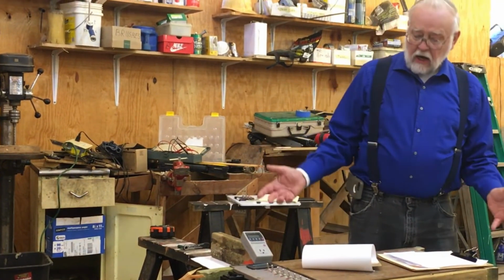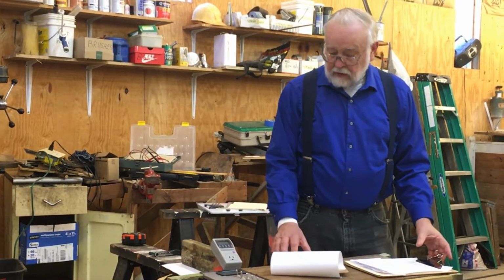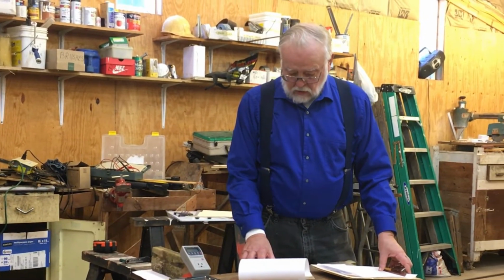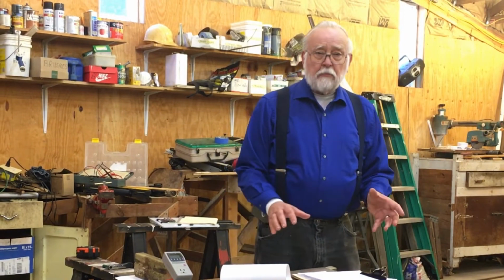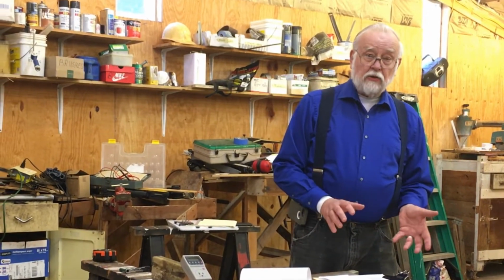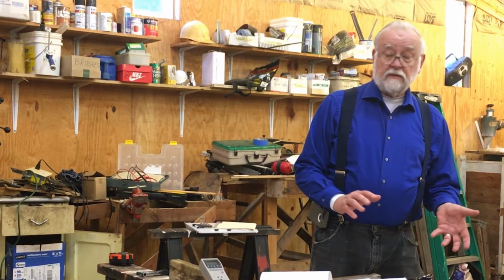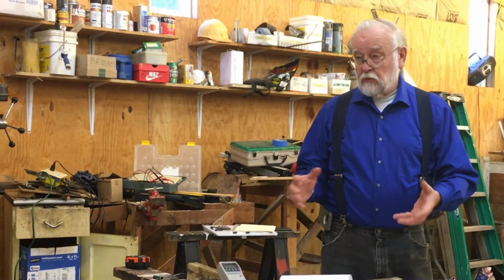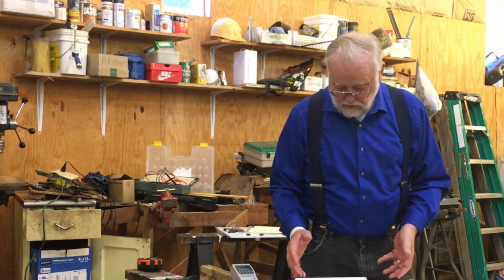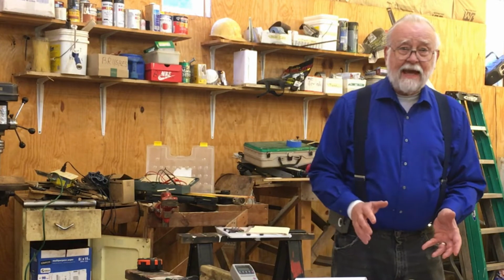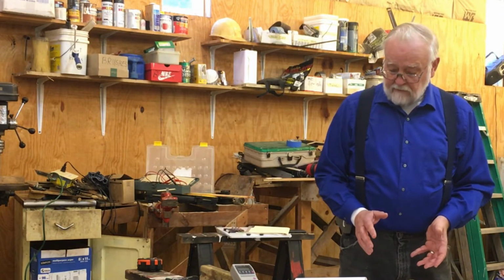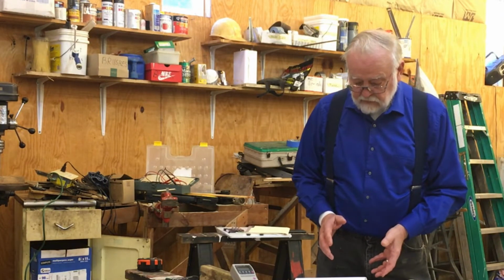What does a generator have to do to meet an electrical load? It must provide an output voltage very nearly 120 volts if it's a 120 volt generator, or 240 if it's a 240 volt generator. And the frequency output must be very near 60 cycles.